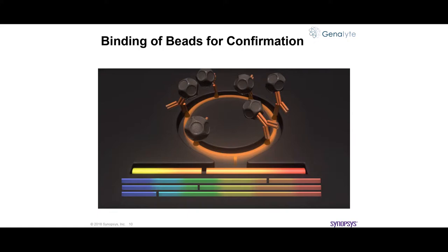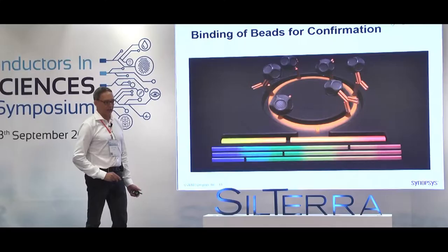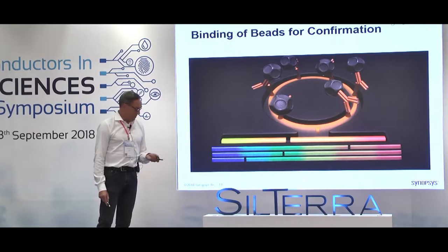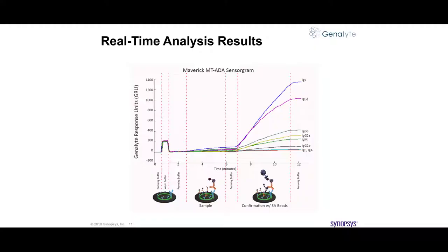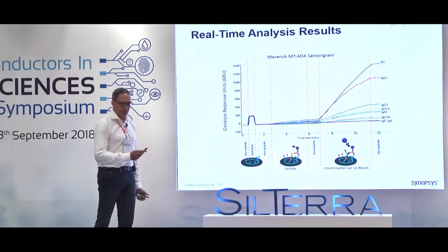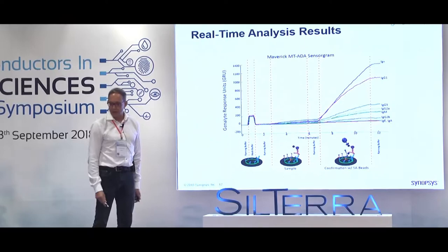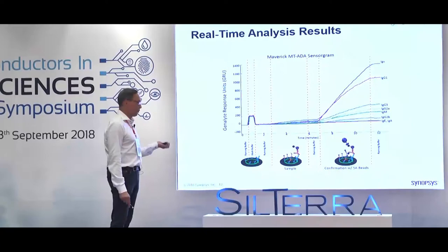Normally the analytes give a weak signal, so you can add beads that bind to the analyte, adding more mass to the ring and giving an even higher frequency shift. If you monitor this real-time frequency shift, you get a signal from all your sensors, and the frequency shift is directly proportional to the concentration of the analytes. This whole test only takes 15 minutes — in 15 minutes you are analyzing 32 different analytes.